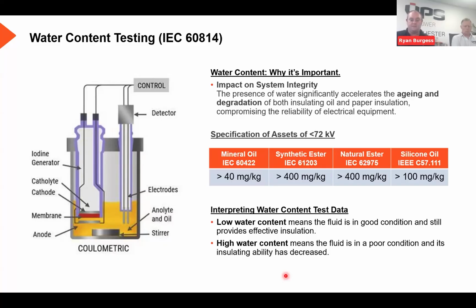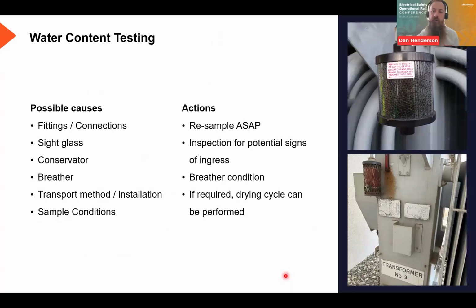That's it on water. Yeah, and then just to continue that on, so again, as Ryan's mentioned, the higher the water content, the lower the dielectric strength, and you've got the potential there to conduct. So in the event of increased water content, there's potential of resulting in flashover, as we've seen with the bushing side of things, with that being one of the things that was detected in the previous sample.